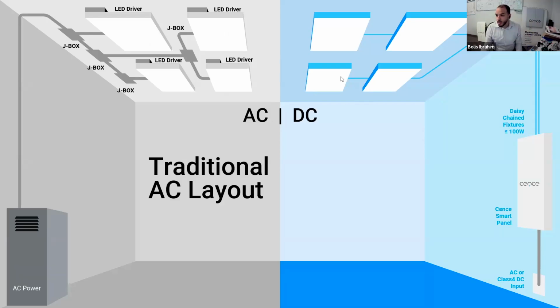Here's an image that someone from marketing made, which is why AC power looks like a filing cabinet—the traditional AC layout has conduit and mechanical protection, junction boxes, and LED drivers. In a DC topology, class 2 low voltage, you use low voltage cable with no mechanical protection, no conduit, no junction boxes. Everything is low voltage, and although you end up with more linear feet of cable because of lower power, 100-watt class 2 low voltage circuits, you get a lower overall cost because you're foregoing the mechanical protection required on the job.